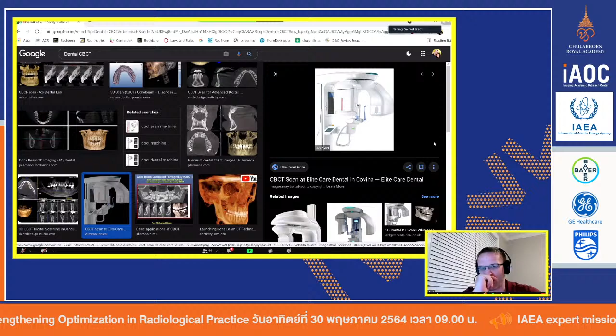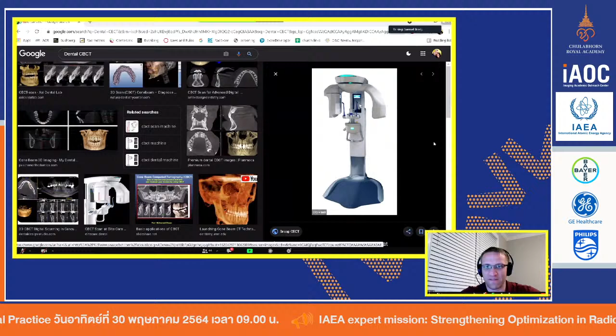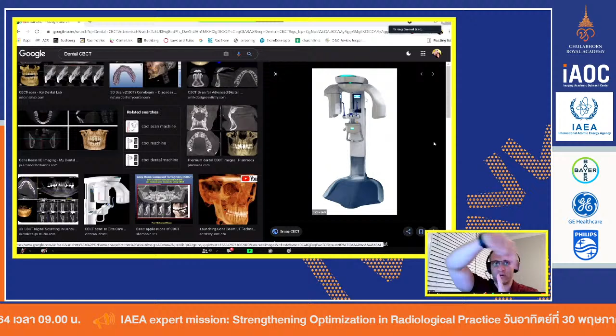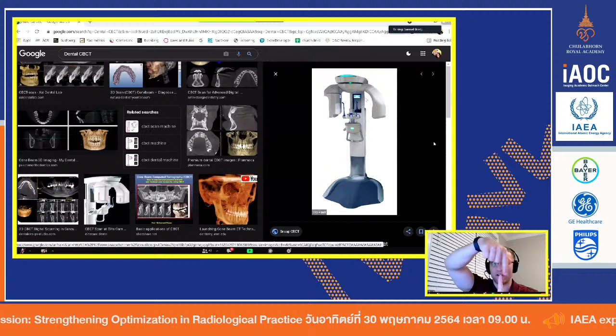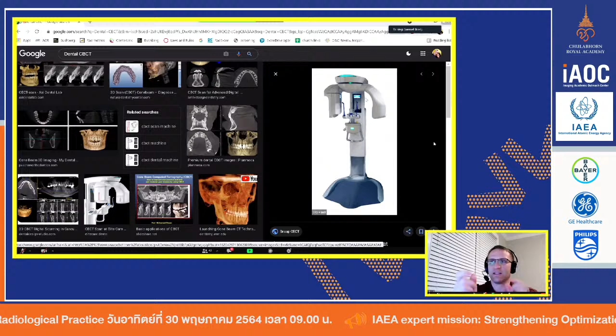The biggest problem with that is when these machines spin around, let's assume we had a CTDI phantom sitting right here. The machine doesn't do a full 360. It will do only part, about three-quarters of the way. So if you put your chamber in the dead center, you'll get one measurement. If you put it over on the left, you get one, and if you put it on the right, you get a different one. The numbers are different.